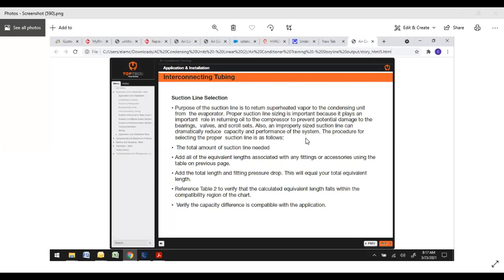Okay, sorry about that. Also, an improperly sized suction line can dramatically reduce capacity and performance of the system. The procedure for selecting the proper suction line is as follows: the total amount of suction line needed, add all additional equivalent lengths associated with fittings and accessories. Add the total length and your fitting pressure drop. This will equal your total equivalent length, and then reference table 2, and then verify the capacity difference is compatible with the application. So ideally, you want to use the correct line size associated with your unit, preferably as short as possible with as few 90 elbows to lower your friction rate.